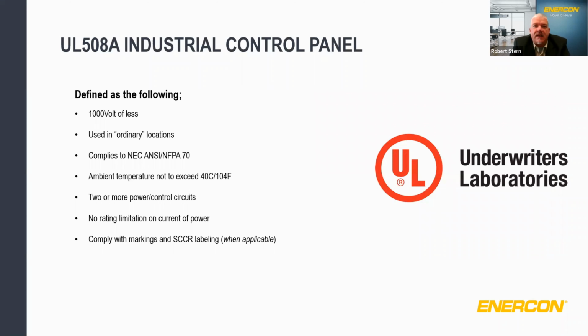The 508A standard for industrial control panels is defined by UL as being 1,000 volts or less and used in an ordinary location. There are control panels used in other locations, and we'll touch on that briefly. They comply with the NEC, ANSI NFPA 70 standard for manufacturing locations, and are to be used in ambient temperatures not exceeding 40 degrees Celsius or 104 degrees Fahrenheit. Again, they include two or more control or power circuits. Under the 508A standard, there is no rating limitation in regards to total power or current. Of course, to follow UL standards, the product must be marked and labeled. In the event it includes power circuits, it must also have a short circuit current rating, which we'll go over. Next slide.